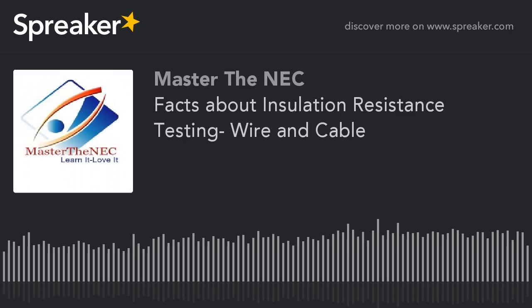When our electricians are out in the field, and they get some wire, and they're actually going to install it in a raceway, or before it's installed in a raceway, they want to check the insulation resistance. And we're going to talk about that, and about some of the manufacturers that produce the megohm meters that are supposed to detect this current that possibly could leak through insulation that is weak or poor.